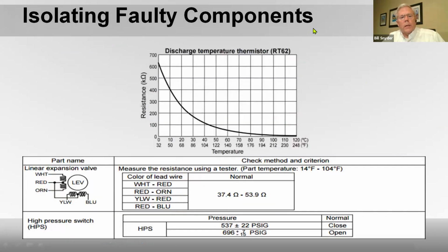Isolating faulty components. The discharge temperature thermistors. This one is for an RT62. They are different. This is not the same chart for every single thermistor, so you'd have to look in the book to verify. But in this case, if you were getting a signal that said you got a bad thermistor, you're getting a flash code. If you're looking at the flash code, it may give you a bad thermistor and that's it. You've got a bad thermistor and there's 4 thermistors on the unit. Now you'd have to pull each one off the board and ohm it out. And if it was, for instance, this is Fahrenheit. So let's just say it was, let's look at something simple. 50 degrees outside and you're reading 400K ohms. You'd say there's nothing wrong with that thermistor, it's fine.